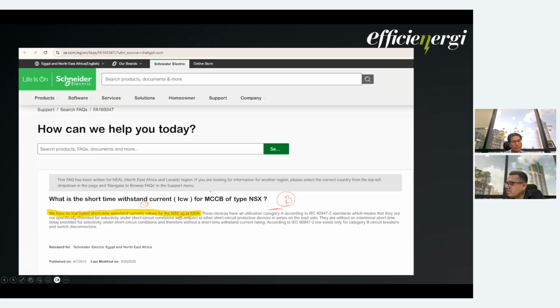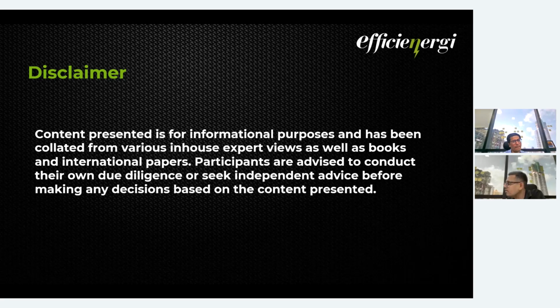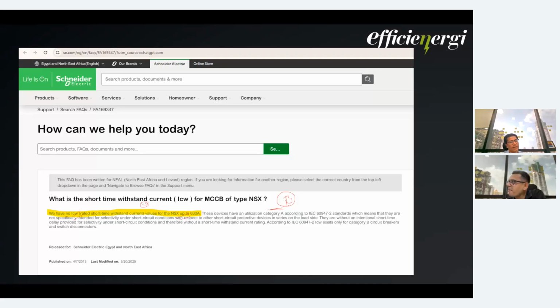And hence, for the case that we described, the only answer is to replace the breakers. There will be no other option by retrofitting some ETU trip unit. Some may give you the suggestion that you replace the ETU, or replace the tripping circuit, or put in some external bypass. But you have to avoid that. This was the webinar basically.